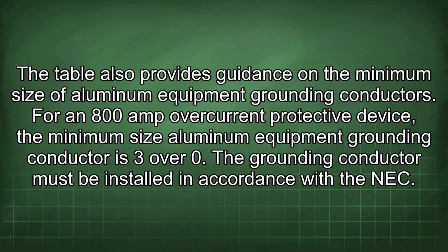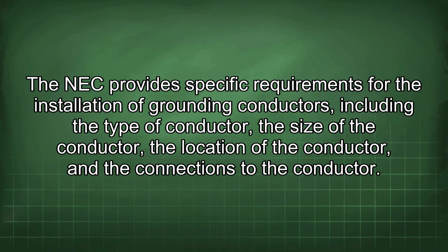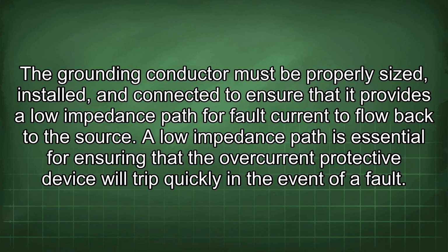The grounding conductor must be installed in accordance with the NEC. The NEC provides specific requirements for the installation of grounding conductors, including the type of conductor, the size of the conductor, the location of the conductor, and the connections to the conductor. The grounding conductor must be properly sized, installed, and connected to ensure that it provides a low impedance path for fault current to flow back to the source.